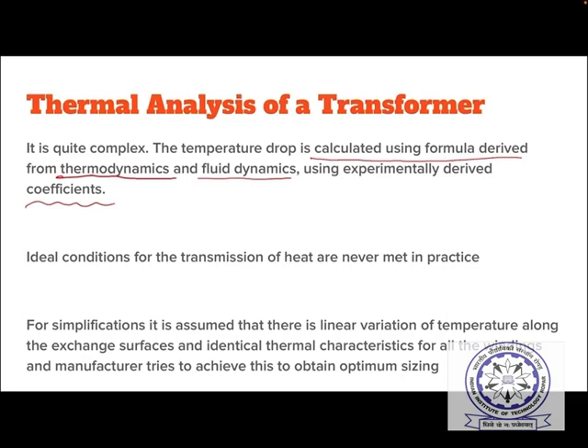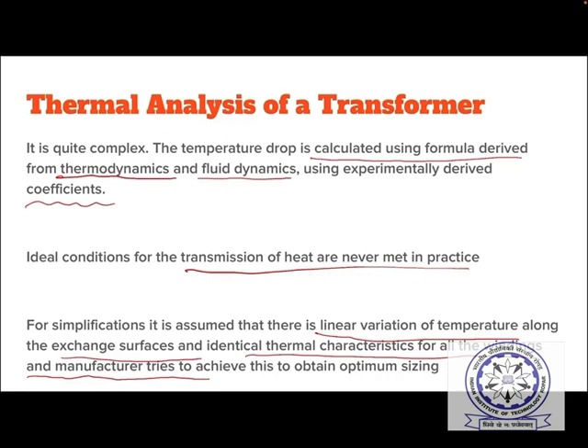Ideal conditions for the transmission of heat are never met in practice. For simplification, it is assumed that there is linear variation of temperature along the exchange surfaces. Exchange surfaces means inside the transformer we have windings, and there is a tank, and there is a radiator, an external cooling system. On all these exchange surfaces, over the height, we assume linear temperature variation. Actually, it is non-linear and quite complex, but we assume for simplicity linear temperature variation and identical thermal characteristics for all windings. The manufacturer tries to achieve this to obtain optimum sizing of a transformer.